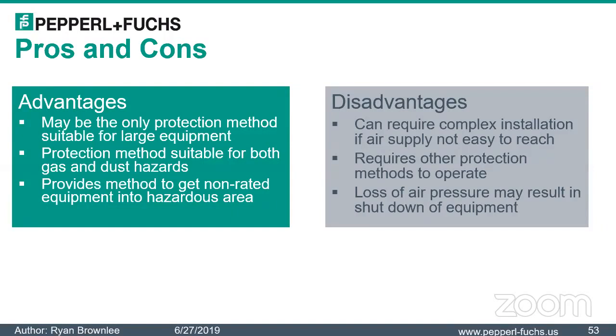Again, air supply. The enclosures have to be braced, because some people purge enclosures that are not rated to. They swell up. Things happen. So you've got to use the right equipment again, and that's what Catherine's here for. Also, with things like an IO or the IS touchscreen on a large purge cabinet, stuff that we do in control panels, sometimes that stuff's not ready to be purged, and the glass will break. We've seen it happen before.